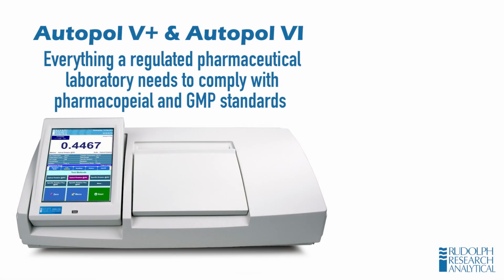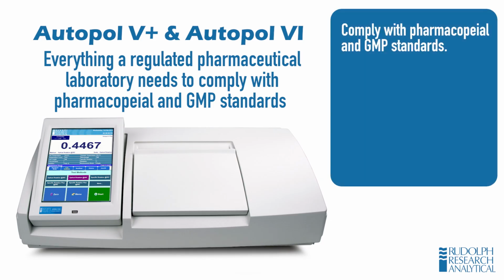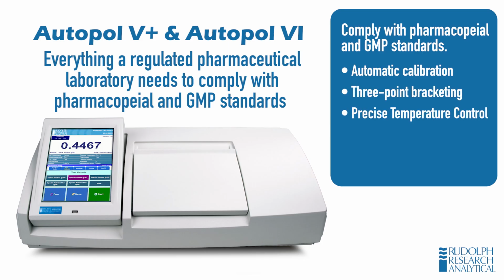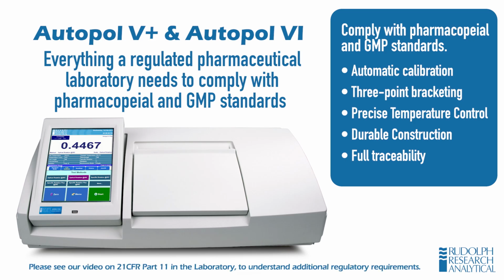In summary, the Autopol 5 Plus and 6 polarimeters provide everything a regulated pharmaceutical laboratory needs to comply with pharmacopeal and GMP standards. Automatic calibration, 3-point bracketing, precise temperature control, durable construction, and full traceability make daily compliance simple and dependable. Please see our video on 21 CFR Part 11 in the laboratory to understand additional regulatory requirements.